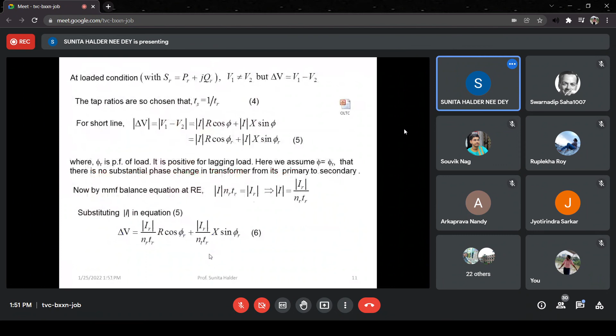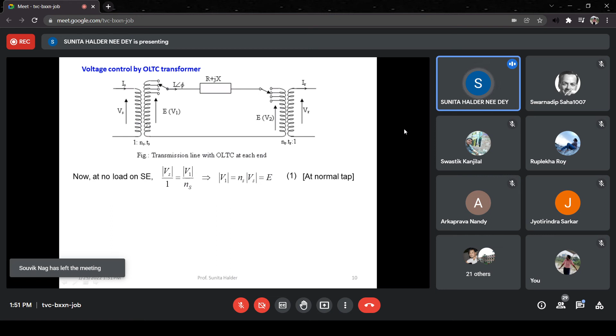Next is the booster transformer. So a regulating transformer may be connected at the end of the transmission line and at the sending end. But this OLTC construction is very difficult, and for that reason its cost is very high. It is not possible that every 50 kilometers you put an OLTC and improve the voltage drop in a line. And for a long line, it is not possible to maintain the voltage drop within a desired value. It may be a high voltage drop which is not controllable using OLTC by tap changing only.